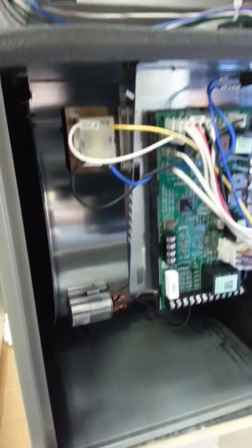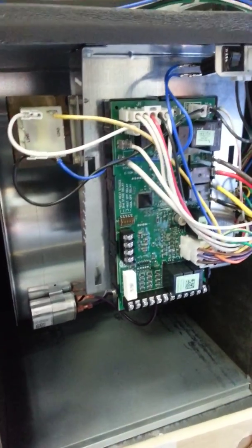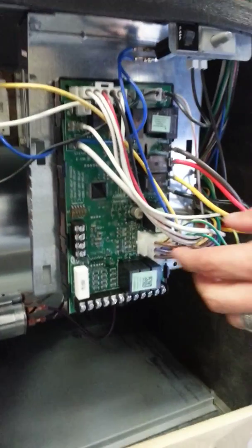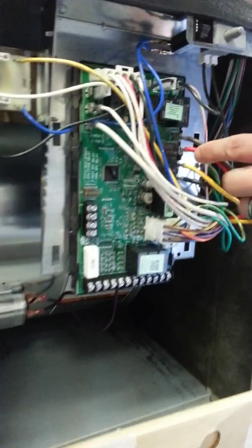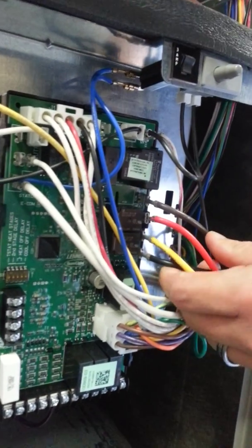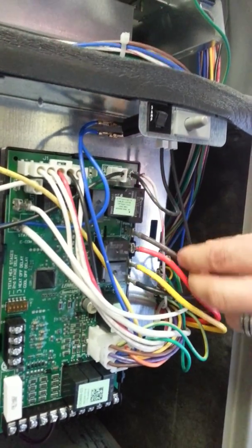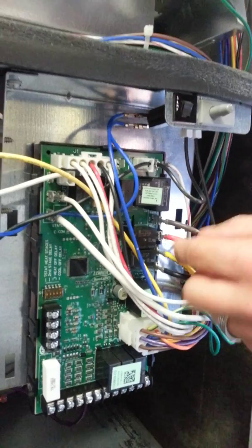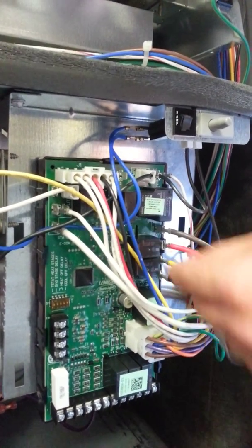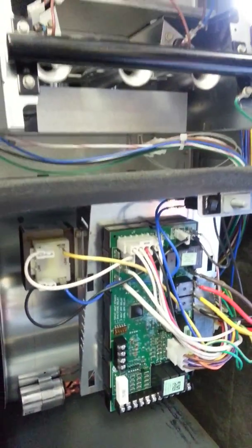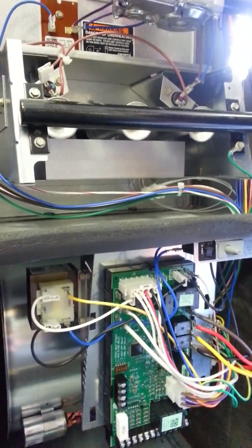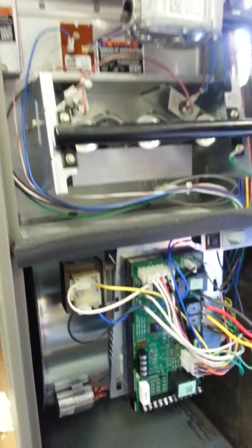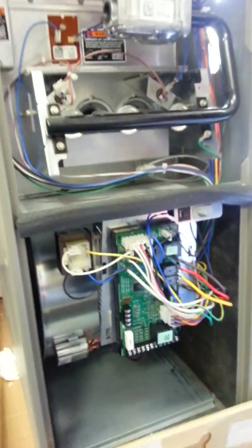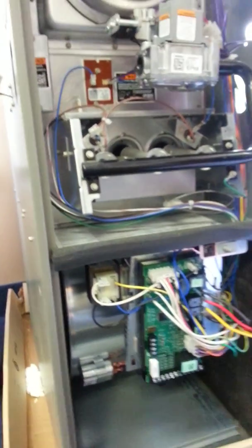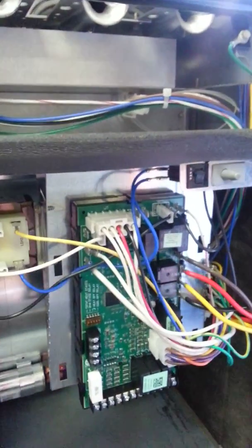And with the blower motor down here, is there a way to change the speeds? Yeah, on this particular one, these three wires are your speeds. Two of them probably say park or spare on it. You can adjust them accordingly. Black is typically high, that's what they come set on usually. Sometimes somebody will get it on high and it's just knocking the doors off, but you can switch it around.